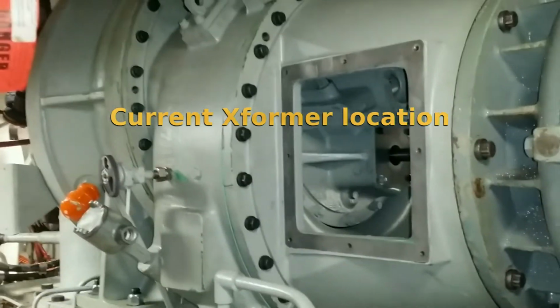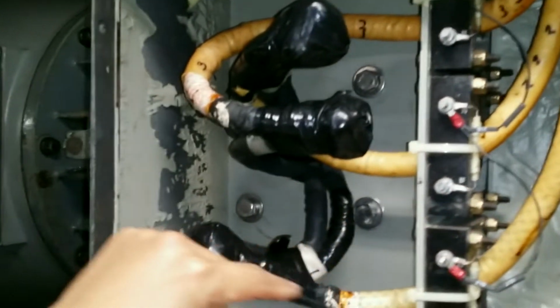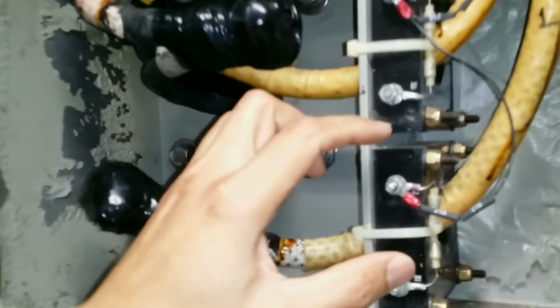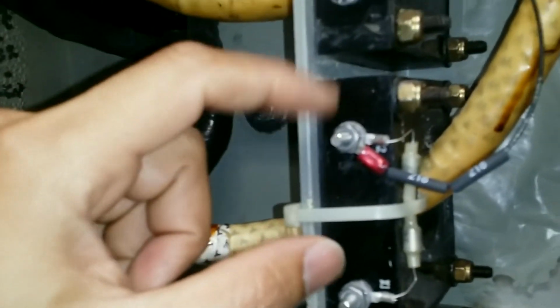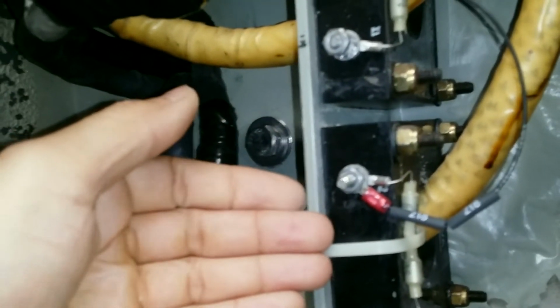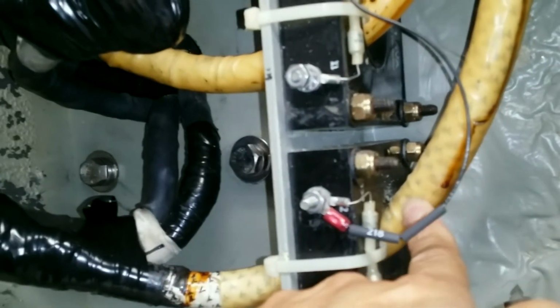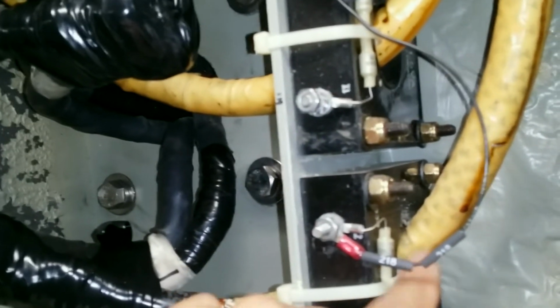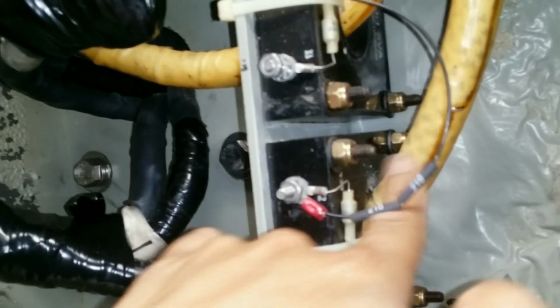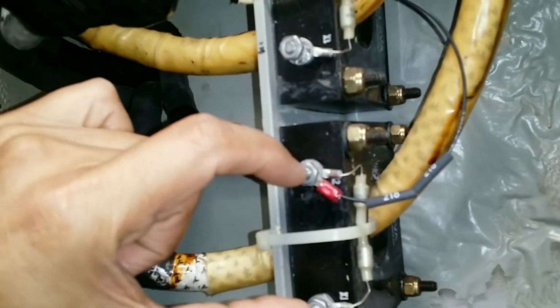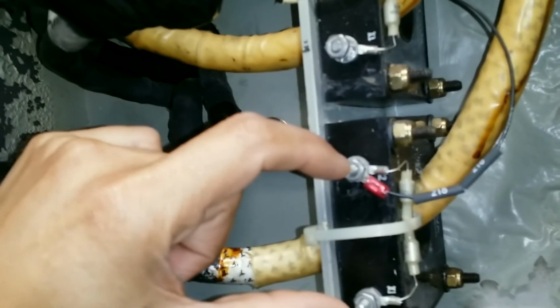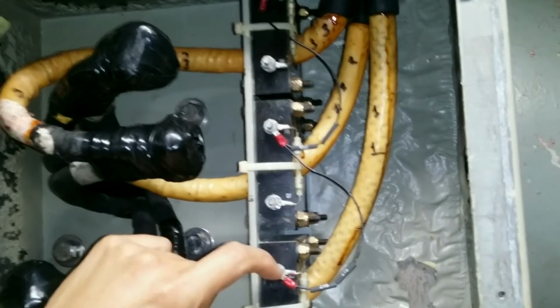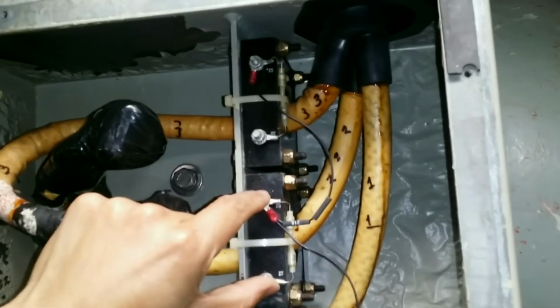So here we've got a 200-ton compressor, and as you can see, this is the motor, and here is the pecker head. You've got alpha, bravo, and Charlie phase coming in to give power to the windings. I want to draw attention to these black boxes. Well, they are current transformers, because a lot of current is going through them. I know it's a single core, single wire, but it still acts as a primary. And then there is a coil winding inside that black circle. These are the two ends of that winding, so that will be our secondary. Obviously, this is the secondary for alpha phase, secondary for bravo phase, and so forth.